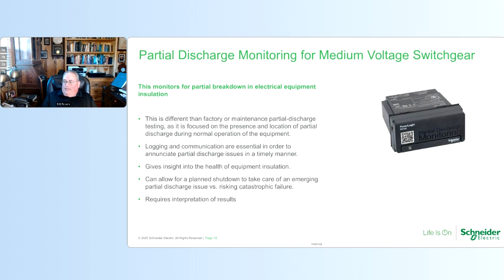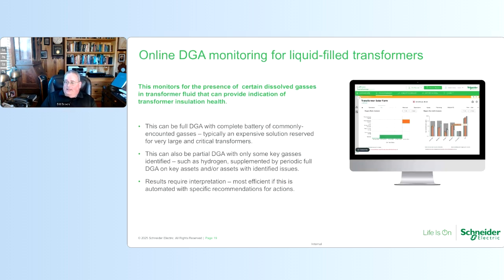At the top of the options list for monitoring of liquid-filled transformers is online dissolved gas analysis, or DGA. Traditionally, dissolved gas analysis was done by periodically sampling transformer fluid and sending it to a laboratory for analysis and interpretation. Over the years, continuous but expensive online DGA options came into the market, but these were generally limited to large and critical transformers due to the cost.